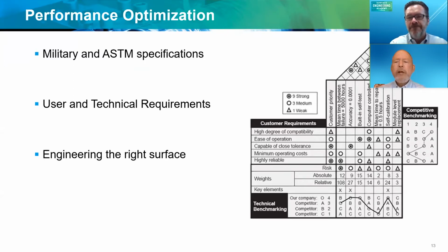Yeah, well, in general, an engineer is going to be presented with a challenge. Here's a product, it needs to do these things. Let's find a specification, whether it's a specification for the material or a coating. And unfortunately, Corey, when it comes to medical devices, there is not a book of medically approved specifications for finishes and coatings. And when you look at all the variability we just talked about, you can see why that would be very difficult to do as well.